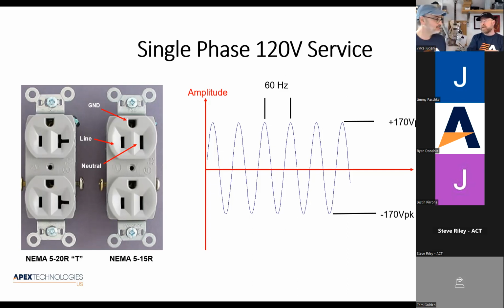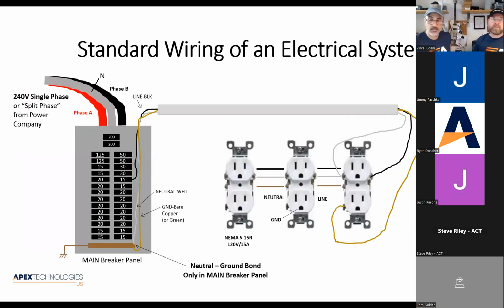But we can go the other way, can't we? Yeah, we can. That's why they make these outlets. A 20 amp outlet will accept both a 20 amp load or a 15 amp load, and that's what we call a T outlet. So anyway, if you're able to spec, and we've got best practices in here, ask for those T outlets so you can plug 15s and 20s in there.